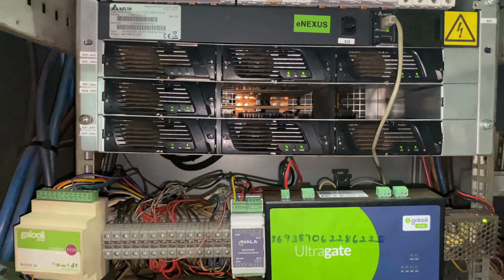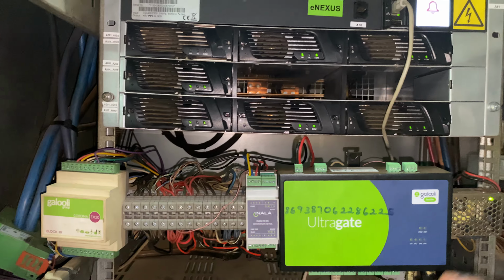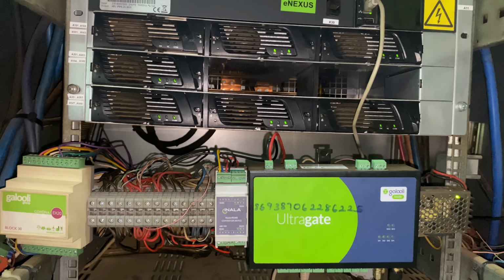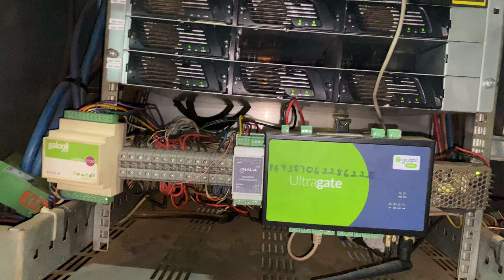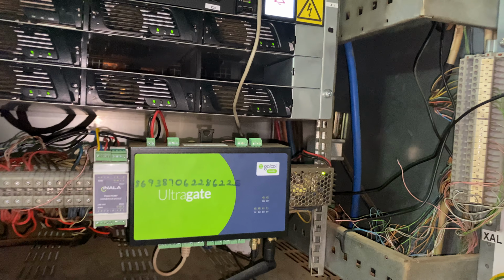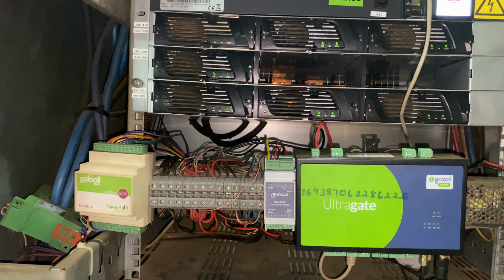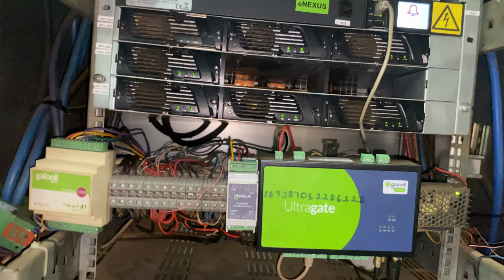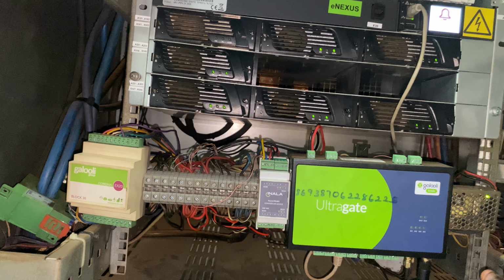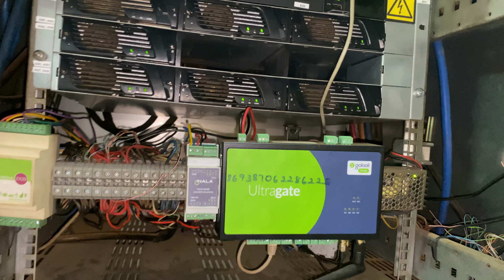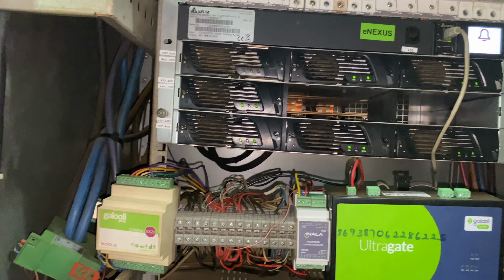So when power reaches this rectifier module, it is converted from AC. You remember the AC we always use in our telecommunication site is three-phase AC power, in a range of 415 volts. When it comes here, it is converted to negative 48 volts DC. That is the suitable and standard voltage we use at the telecommunication site. When it reaches the rectifier module, they give this power to the bus bar. Are you seeing that golden bus bar behind?